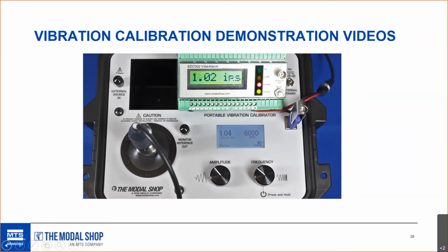It's quite often not so much creating calibration certificates as it is just verifying vibration alert and alarm shutdown values and shutdown logic. Right. I'm just catching up with you here, Mike. I'd like to point out that the actual accelerometer is mounted on the lower left. This is the accelerometer that's connected to the vibe alarm, and its readout is the green, and the readout for the reference accelerometer buried inside this unit in the shaker is in the blue.